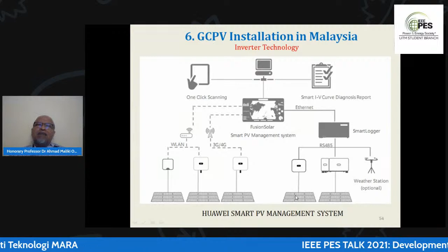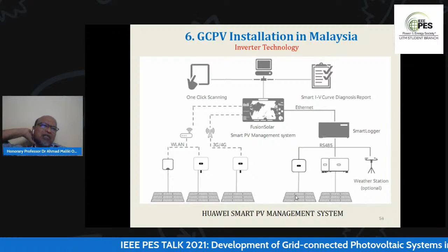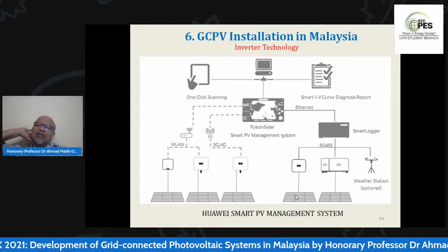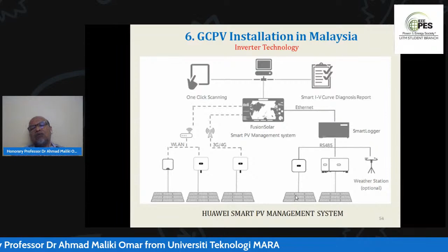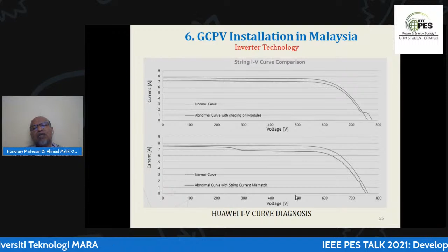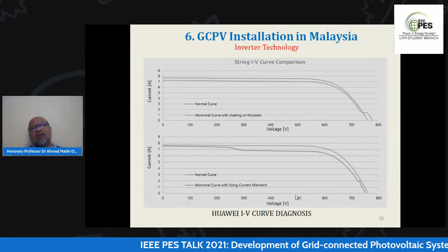This is very important for those familiar with the IV curve. We can instruct the smart logger, and through the smart logger instruct the inverter to perform IV curve tracing for every string. Traditionally, we take very specific equipment to do the IV curve manually, but now you just send a signal to the smart logger to perform it. This is a fantastic, excellent technology that can help you a lot to diagnose the system. This is how it looks, where you compare the IV curve and can detect anything happening to the string, without detaching the system.